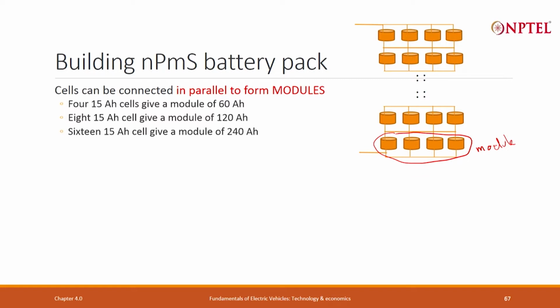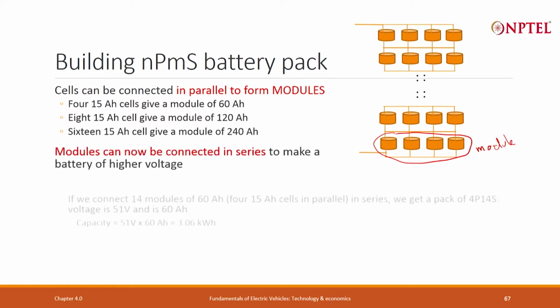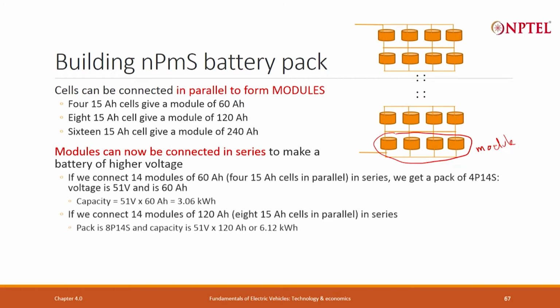Now you connect the modules in series to make a battery of higher voltage. If you put 14 modules of 60Ah, you get 4P14S, 51 volts, 60 ampere hours, a capacity of 3.06 kilowatt hours. If you connect 14 modules of 120 ampere hours in series, you get 8P14S, or 6.12 kilowatt hours.